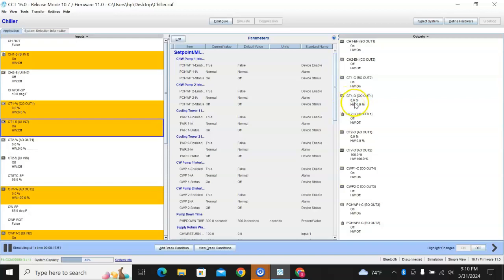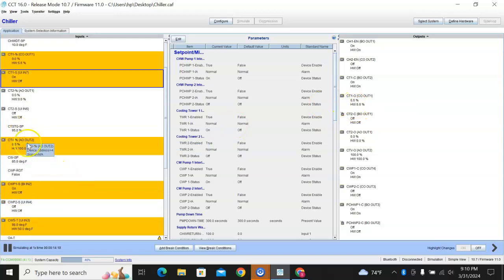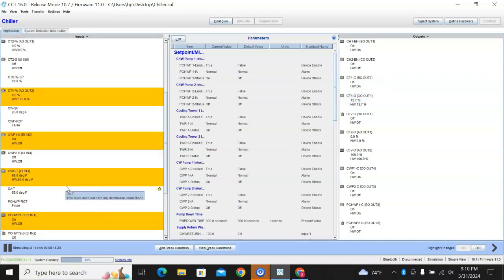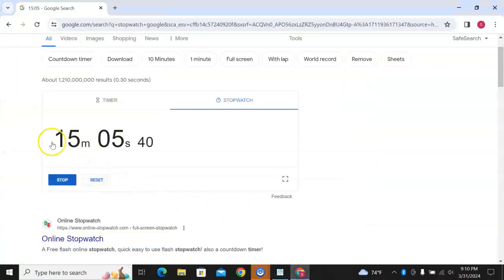And it's a 6% fan. So really, that's the minimum, whatever you set in the drive, 20 hertz. So we got one fan on, 20 hertz. Water is hot, 98, probably close to 100 by now if I would have kept jumping it up until the fan came on. 13%. You know, this is going up, and I'm just going to stop it right now, 15 minutes.